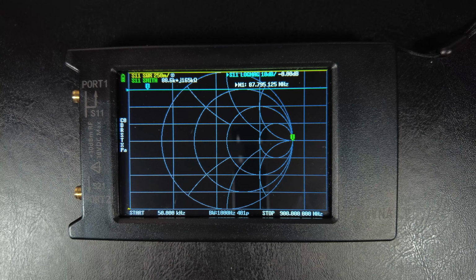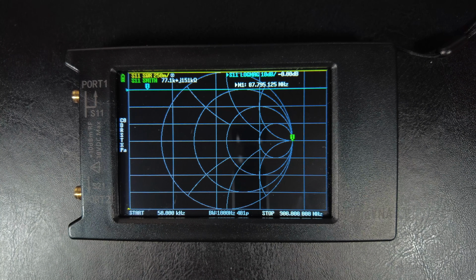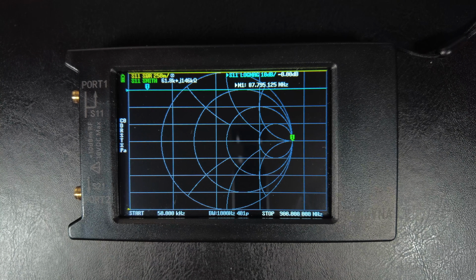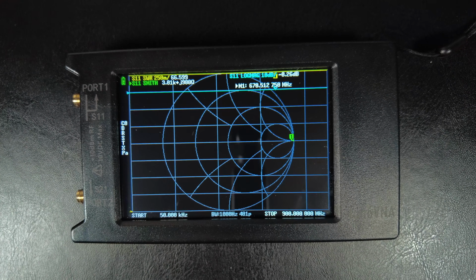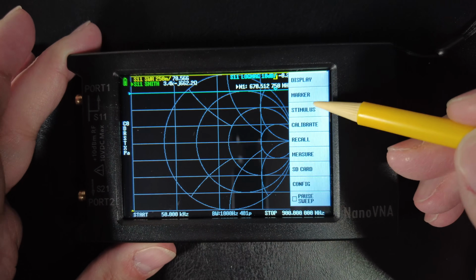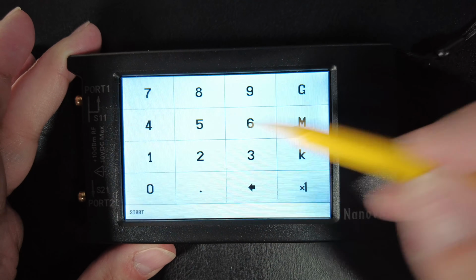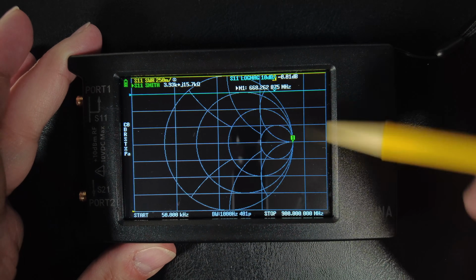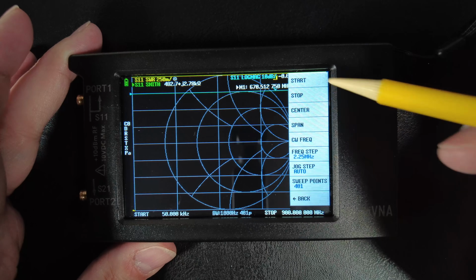Okay, so the first step we're going to do here is set the start and stop frequency to something that makes sense for how you intend on using your coax. If you're going to use it for HF, then you can set your frequency range from, say, 50 kilohertz to 30 megahertz. If you're going to be testing for VHF and UHF, set your range to something like 50 megahertz to 500 megahertz, or even 50 kilohertz to 500 megahertz. And make sure that you're scanning with 401 points to get your highest resolution.